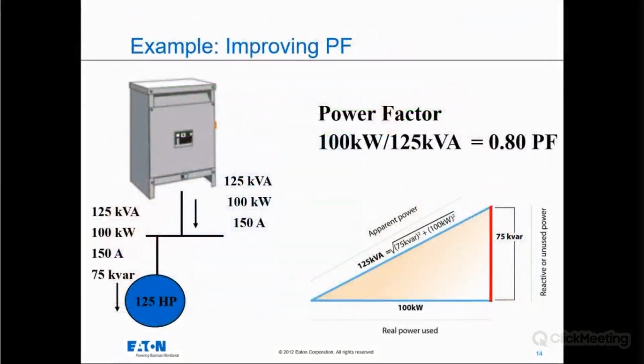So let's take a look at a sample and example. If we had a 125 kVA transformer and you wouldn't load it all the way up to 100%, but in this example, for simplicity, let's load this transformer all the way at 100% load, which would be putting a 125 horsepower motor on it. The motor wants to draw 150 amps and 75 kVAR. Again, it's drawing some ratio of kVAR and kW through that transformer uncorrected.